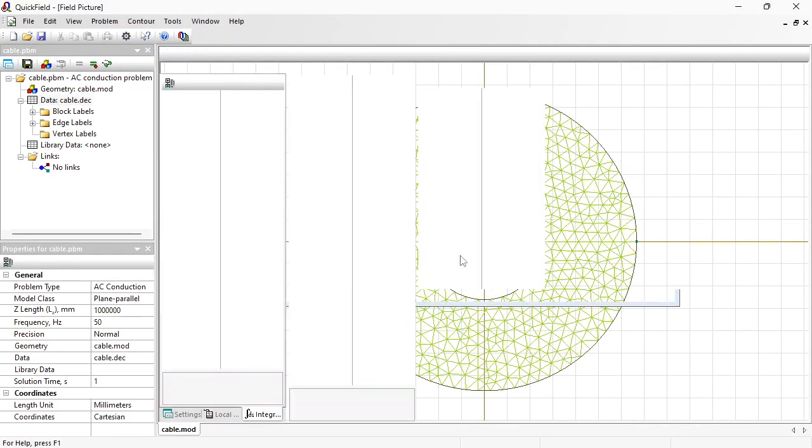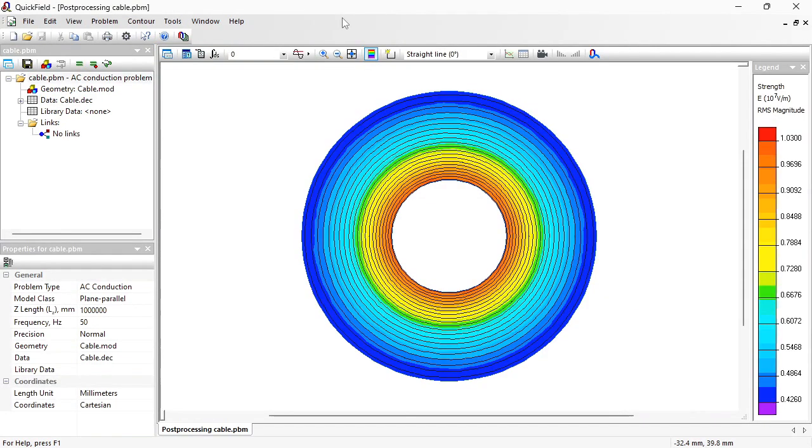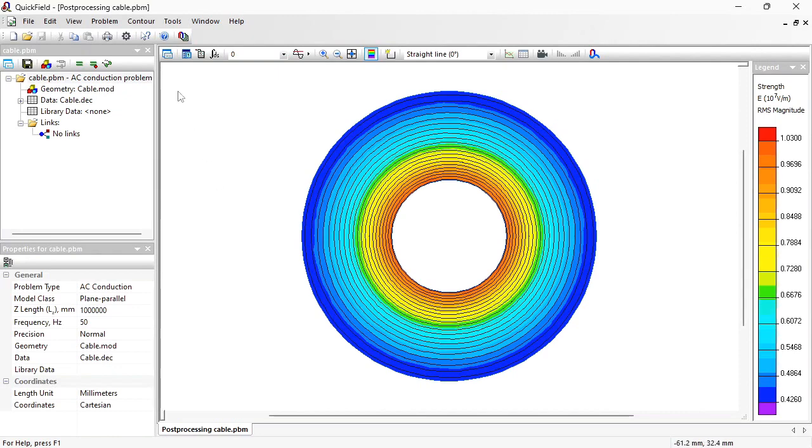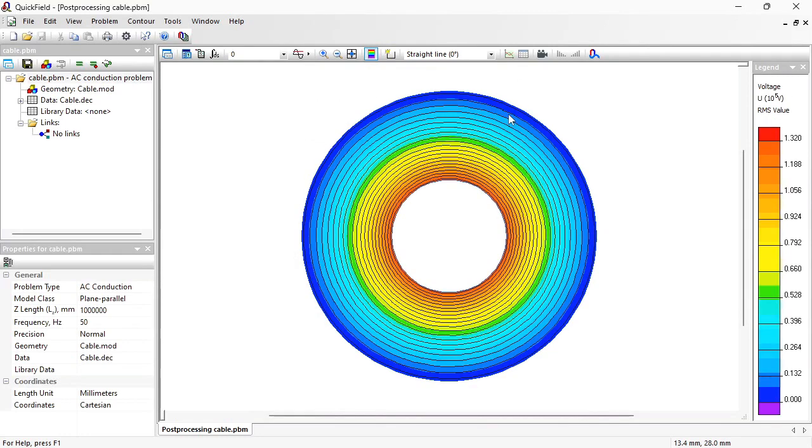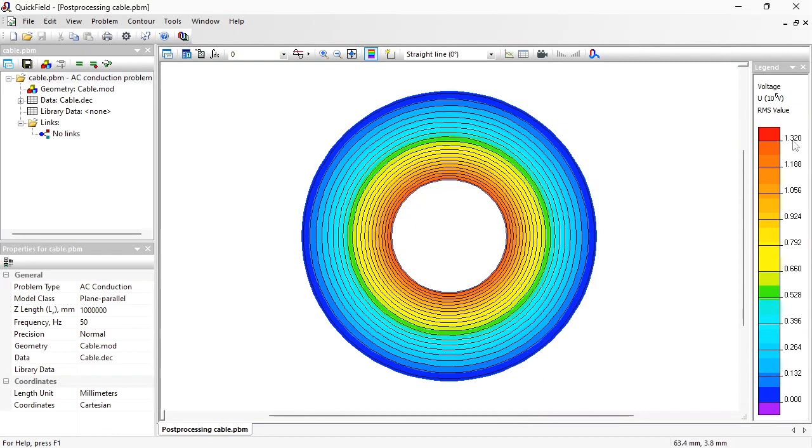Let's take a look at the results. Here you can see the electric stress color map and the equipotential lines. Let's adjust the field picture. I will switch on the color map of electric potential. Now you see indeed the screen is grounded. It has zero electric potential and the conductor electric potential is 132 kilovolts.